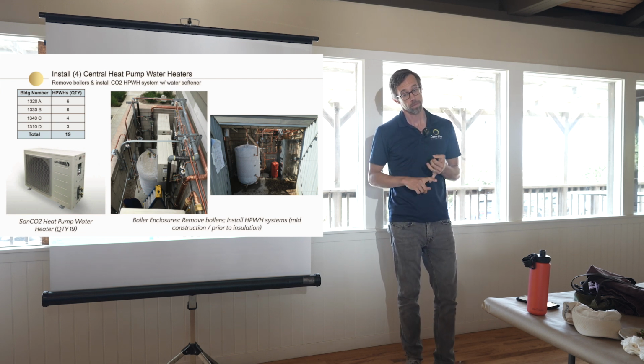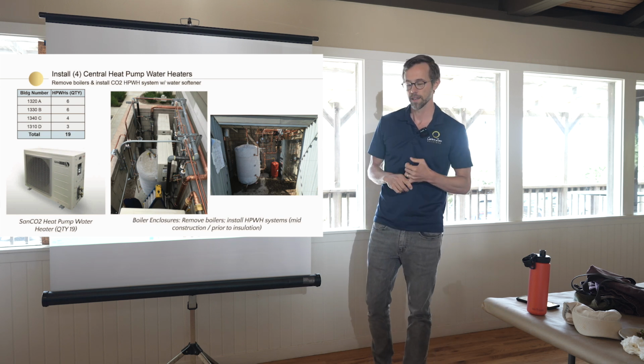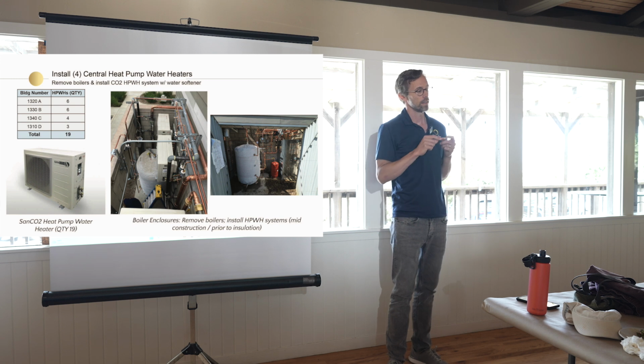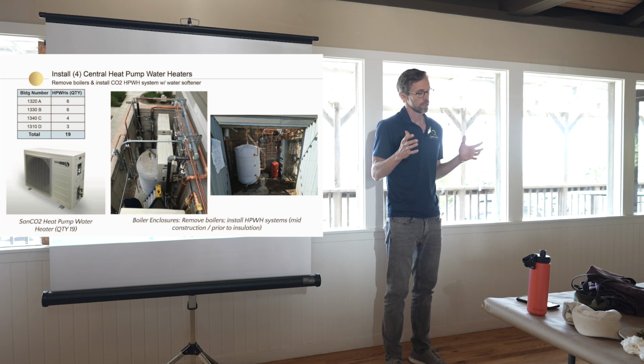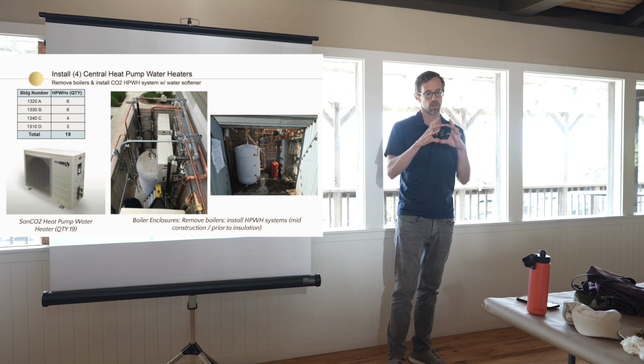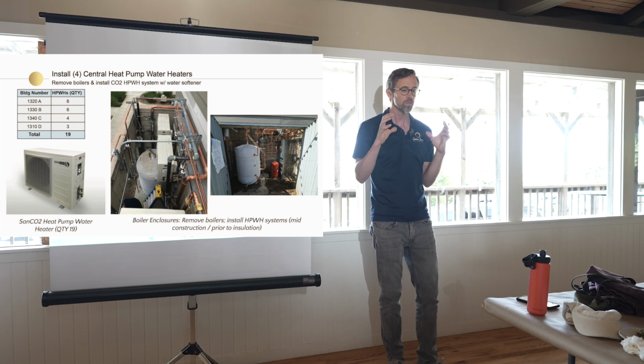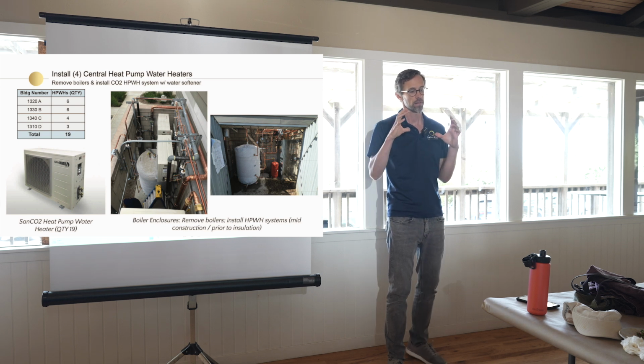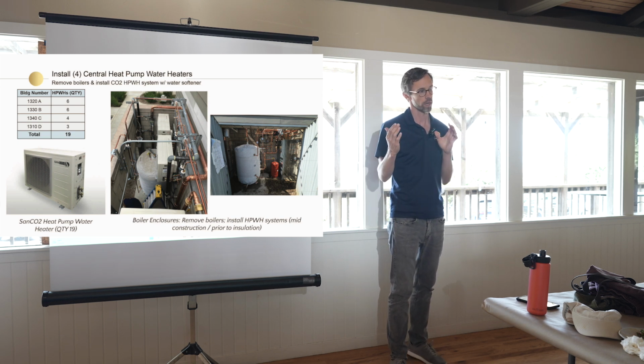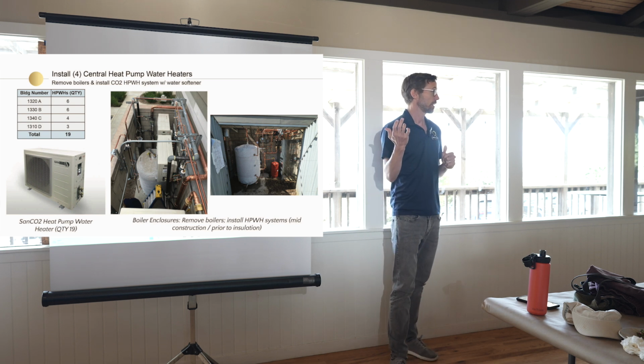It means the contractor who installed it got to charge a lot more originally, back in the original building days. But it also means you have a much harder building to deal with because the pipes are so oversized, pi r squared. If they have a 4-inch pipe, but they really only needed, say, 1.5 inches, you've got maybe 5x the cross-sectional area, which means your flow rate will be 1/5. So it just takes that much longer to get hot water out.